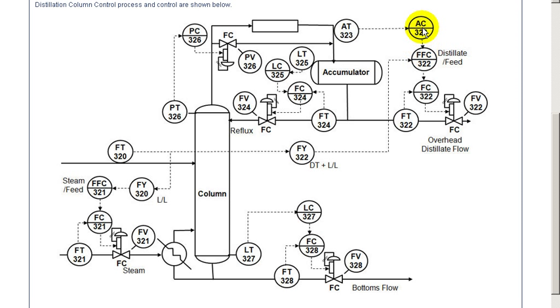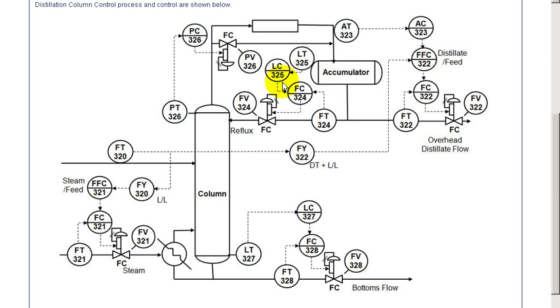The composition of the overhead is measured. The light component is measured there and based upon that we're adjusting the distillate to feed ratio. The level of the accumulator is maintained by adjusting the reflux flow.